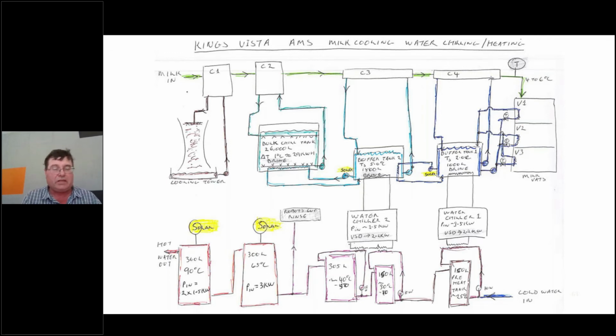So as you can see, the milk comes in the top left-hand side, goes through a cooling tower cooler, bulk chilled water tank, through cooler 3, cooler 4, and into one of 3 vats. And then each progression is a different temperature. Cooling water is at whatever the cooling tower is at. The bulk tank at the moment is sitting around about 10 degrees. Cooler 3 sits at 5 degrees in that buffer tank, and the cooler 4 sits at about 2 degrees, 2.2 degrees in that buffer tank. As you see, there's 2 water chillers running it, or what I call water chillers.